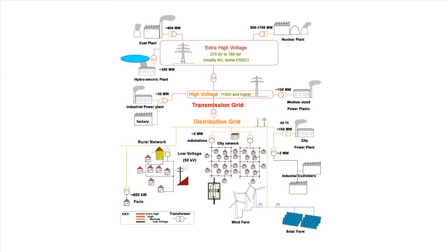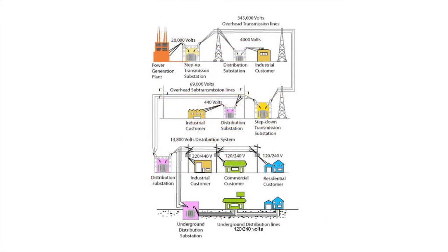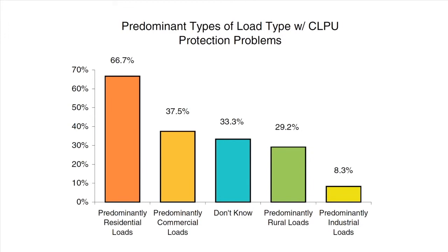The ADVC cold load pickup function. When a typical heterogeneous load has been without supply for a period of time, as in hours, it loses its diversity. After supply is restored, the load is higher than before the loss of supply because all heater, refrigerator, or air conditioner thermostats have turned on. The longer the time without supply, the greater the loss of diversity. Therefore, the higher the load current after supply is restored. This increase in load current may cause overcurrent protection elements to operate.